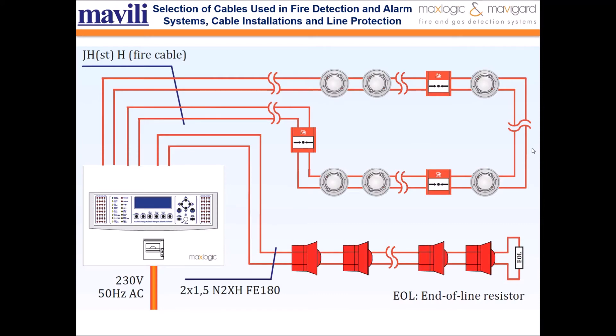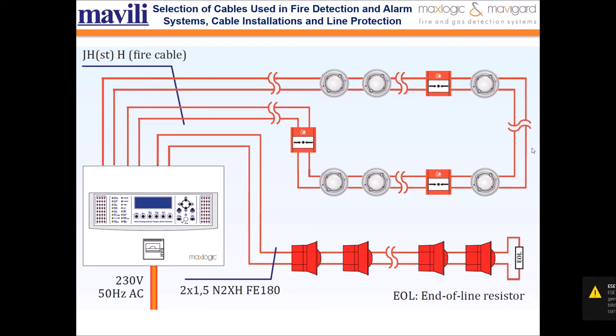The cable which is connected to the sounder beacon, like output devices, must be fire resistant. But the cable which is connected to the detector and manual call point, like input devices, might be either. According to standards, the cable resistance against fire must be minimum 30 minutes.